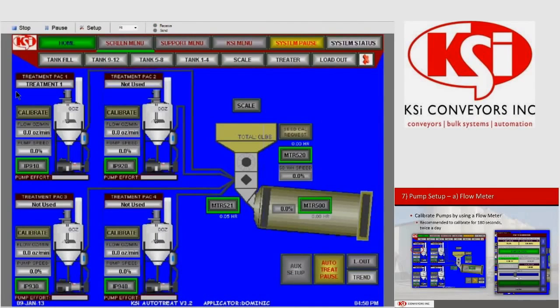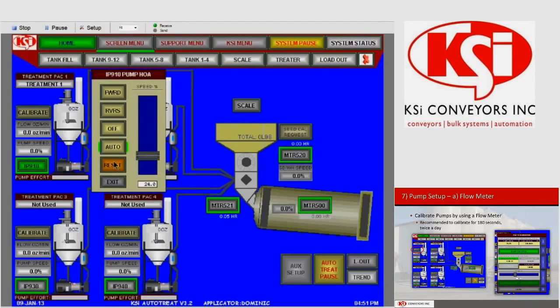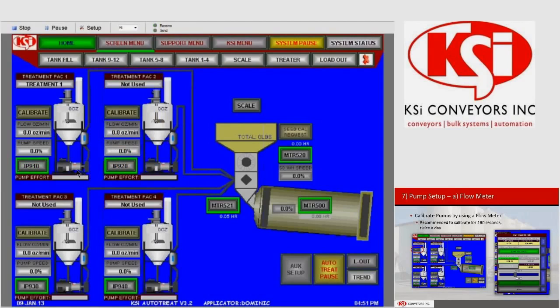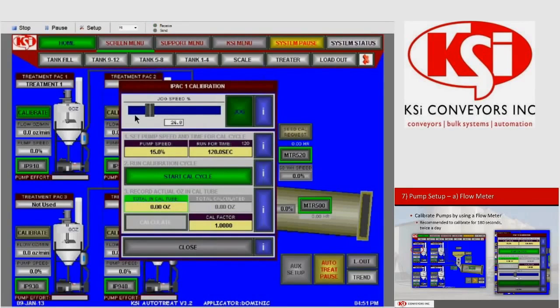and to begin with, we want to make sure we turn our valve so that our liquid will be flowing back up into our cal tube, and we need to get liquid to the 0 line on our cal tube. So to do this, we can select our IP910. We can turn our pump in forward and set the rate, put it in forward and let it go up above the 0 line and then drain it back down. Or alternatively, if you press and hold right on the pump from this graphic, your pump is going to run in jog mode until we release it. When we release it, we then go over to our valves and switch the valve so that it is at the 0 mark.